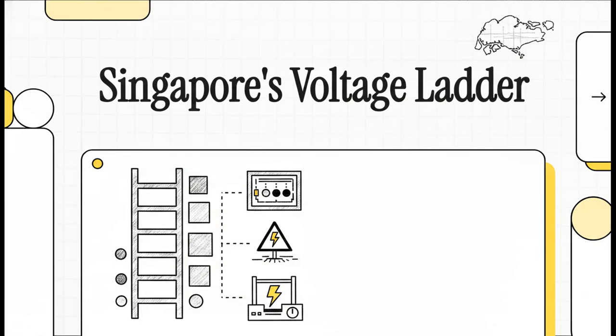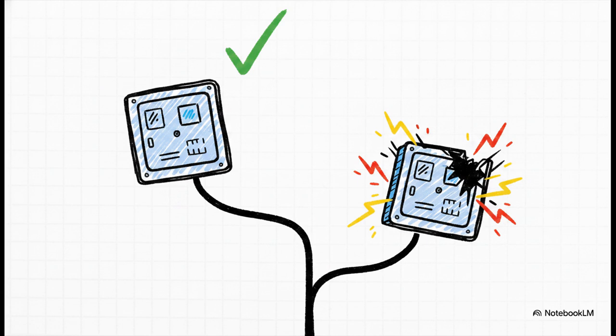Let's dive right into this explainer by locking down the single most crucial framework for Singapore's power grid. We're talking about the voltage ladder. Here's the deal. Every single engineering and regulatory decision made about this grid, from which switchgear to install to what earthing method applies, traces back to one foundational number. What voltage tier are you in? Get that classification wrong, and literally every downstream calculation is ruined. We're talking about the difference between a fault that trips safely and one that turns a substation into a massive hazard. There's absolutely zero margin for error here.